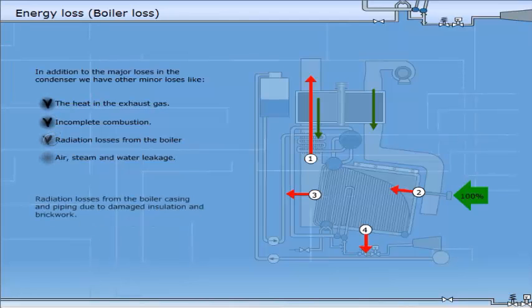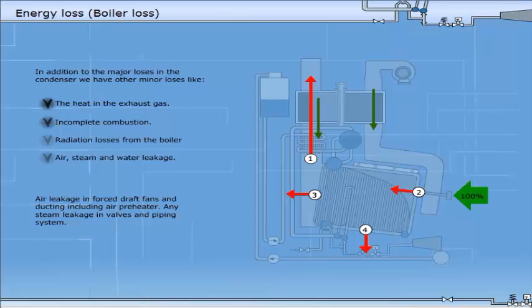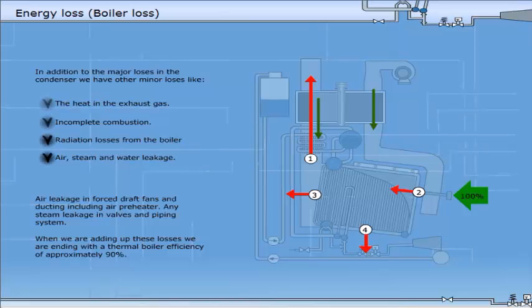Radiation losses from the boiler casing and piping due to damaged insulation and brickwork. Air leakage in forced draft fans and ducting including air preheater. Any steam leakage in valves and piping system. When we add up these losses, we end up with a thermal boiler efficiency of approximately 90%.